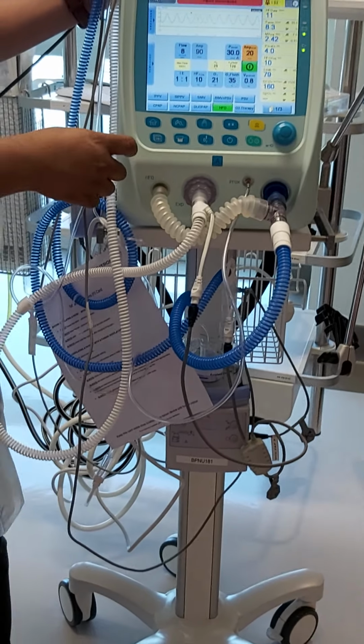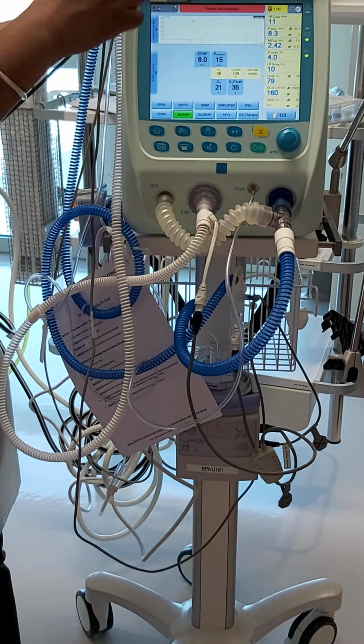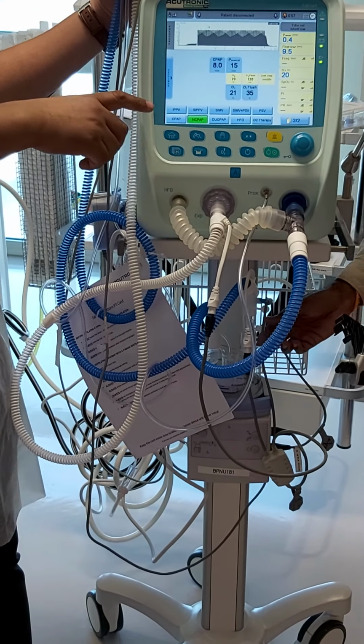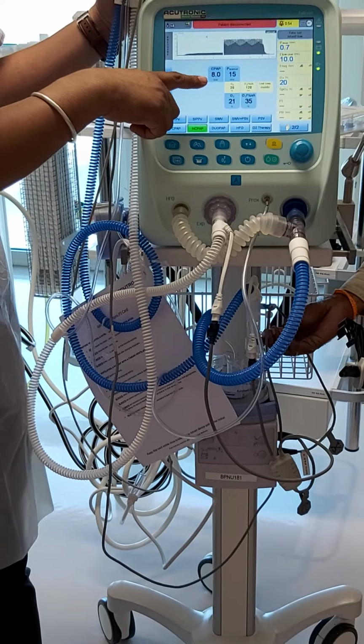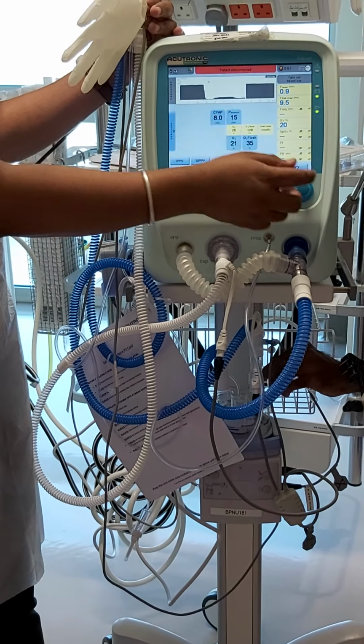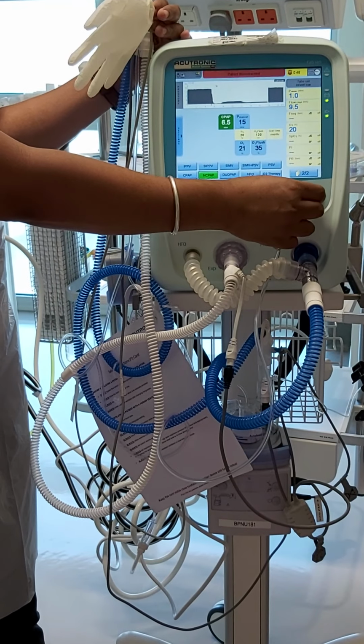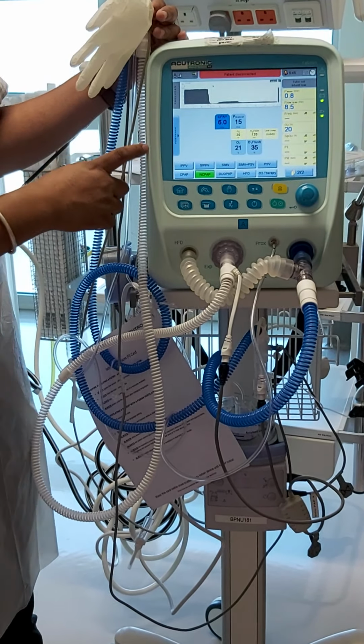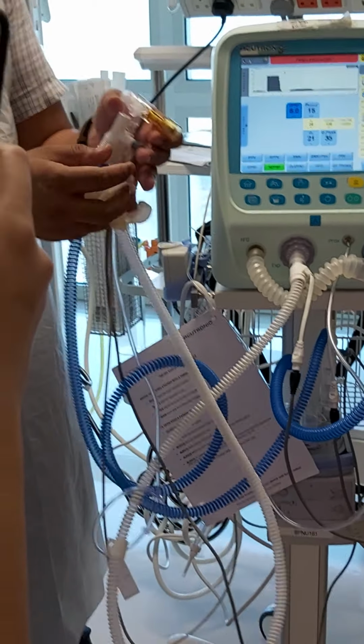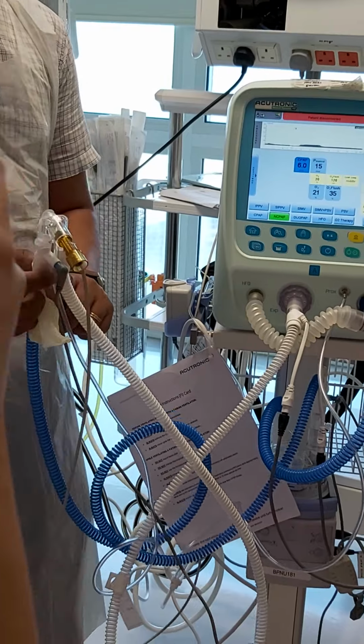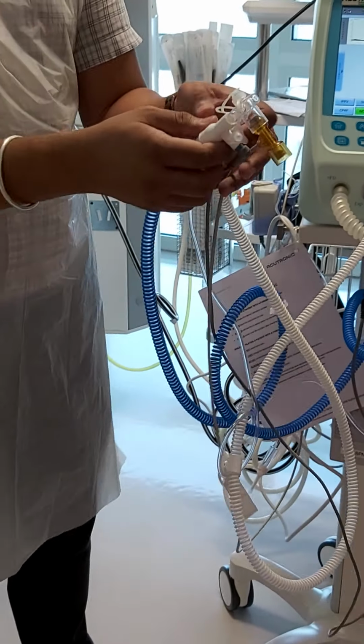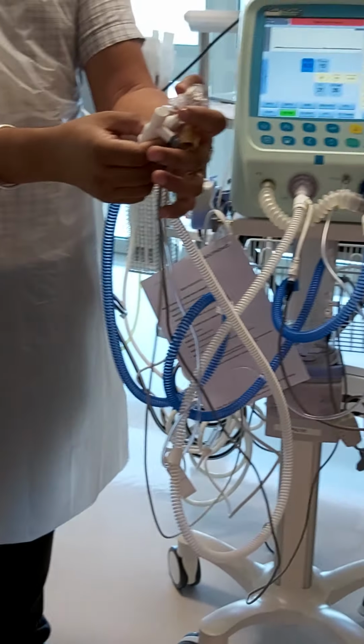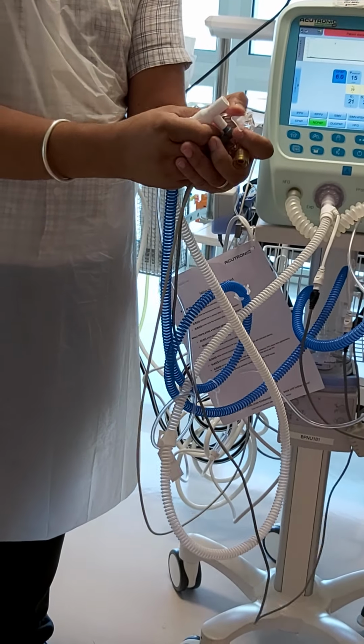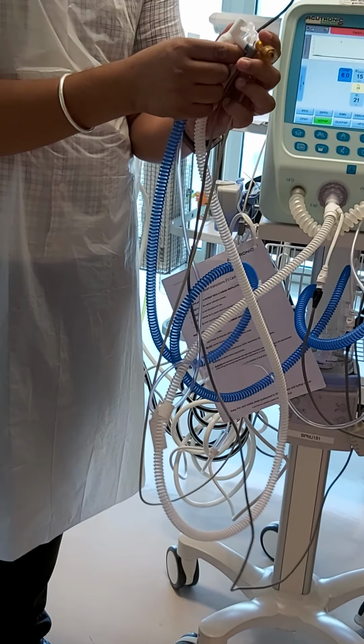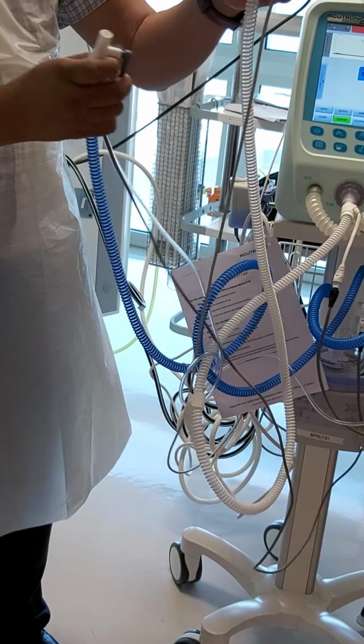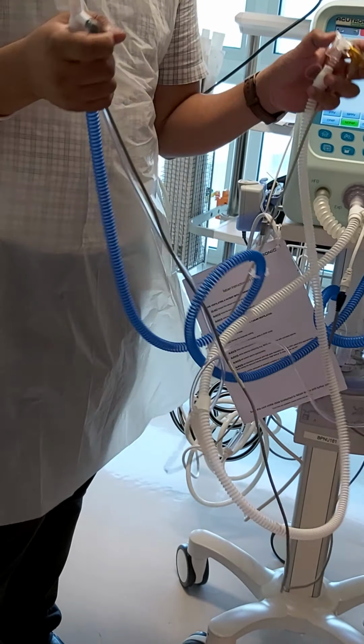Okay, so now we'll go to NCPAP. Your NCPAP is like your CPAP. Your CPAP will have one pressure. That's your CPAP pressure. Now you can adjust that on your own. You don't need to adjust the flow. Then you can confirm. And then with CPAP, what you can do now is you will have to remove. CPAP is just single limb. It just measures pressure. So what you can do is I can get this, and I can get this one. You don't need to throw away the remaining parts because if ever the patient will be back on high frequency or conventional, then you can utilize the same.